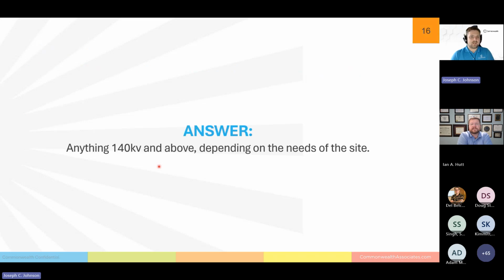The answer is anything 140 kV and above. Now, above with an asterisk, there's a limit. You can't go too big because otherwise it won't work. But we're about to go in and look at the needs of the site. A smaller arrestor closer to the actual line to ground voltage has more risk of conducting more during these TOV events, as Ian was mentioning. And if it's below 133 kV, which are options 1 and 2, you actually will be conducting at normal system voltage, and your arrestor will be conducting continuously, and it's not going to last very long.